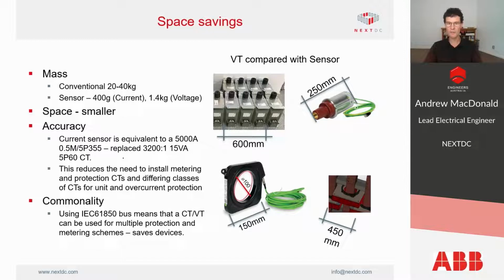The accuracy is better, so the current sensors that we are using are equivalent to a 5,000 amp 0.5 metering class CT with also a class 5P 355 protection CT rating. These replaced 3,200 to 1 15 VA 5P 60 protection CTs in our switchboards, which were very large and heavy.